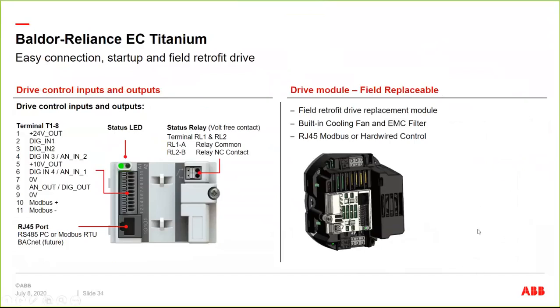This is the drive module under the hood. Just nothing really exciting here. It's a basic drive controller. It's got up to 4 digital inputs or 2 analog inputs. So you can have 2 digital in and 2 analog in. They're dual function digital analog inputs. An analog out or digital out. The standard controller has serial Modbus with an RJ45 port or twisted pair plus minus. And we'll be adding BACnet in a future release as well. And then there's a relay output on it. And again, these modules are fully field retrofittable, have a built-in stirring fan on them. It's not really for cooling, it's just to get even air distribution inside the enclosure with an EMC filter.